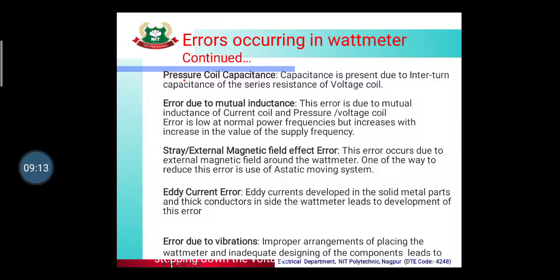There is also an error due to external magnetic field effects. Another error is the eddy current error, which develops in the solid metal parts and thick conductors used in the instrument. The last error is error due to vibration, caused by improper placement of the watt meter or inadequate design of components, which generates vibrations in the instrument.